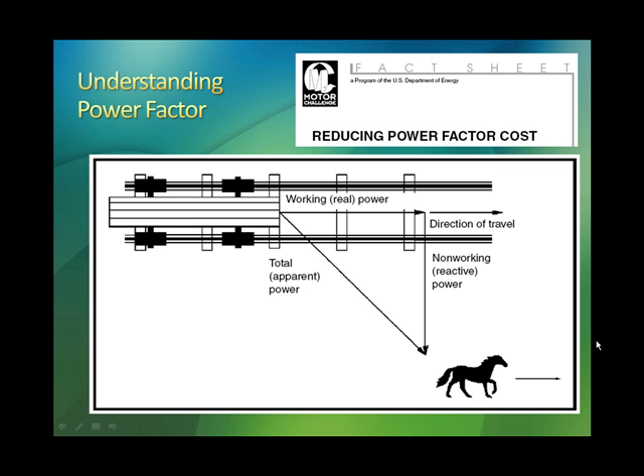Now, if you think about that, if you were trying to pull something, it's not very efficient to pull at an angle. You always want to be pulling straight on. Well, the same applies to electrical power. The most efficient use of electrical power is to have 100% of it working real power. Even the motors prefer to have it that way. When you have all your power as working power, you have a power factor of 1, and the total apparent power and the kW, the working real power, are the same, and there would be no non-working or reactive power. But most systems have some reactive power, so from an electrical standpoint, we're always pulling off to the side.